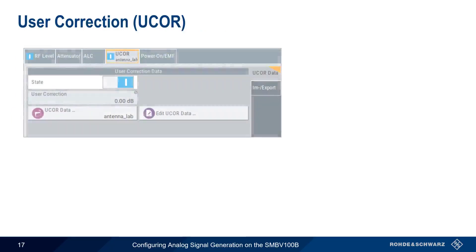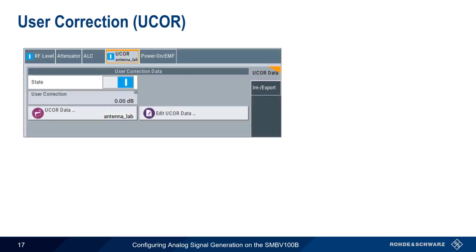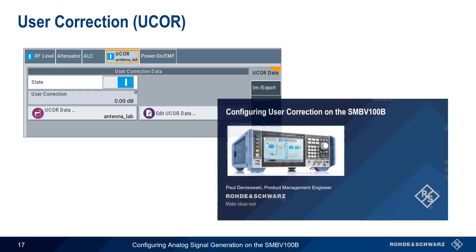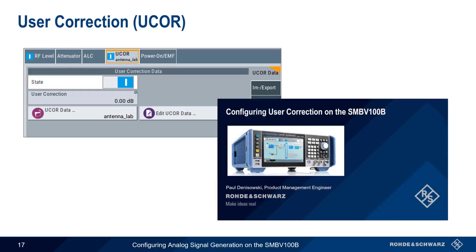User correction allows you to select and or create user correction data. This data is in the form of a file that adjusts the level of the SMBV depending on the current frequency in order to compensate for an external frequency response. If you'd like to learn more about user correction, please watch the presentation Configuring User Correction on the SMBV100B.